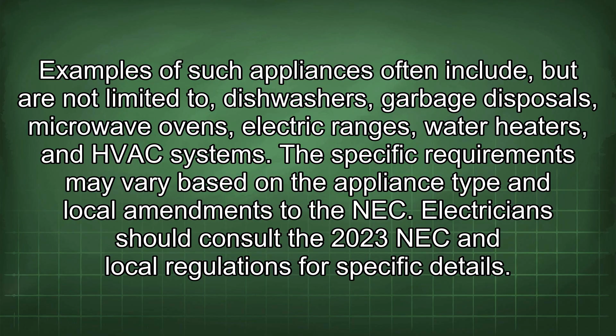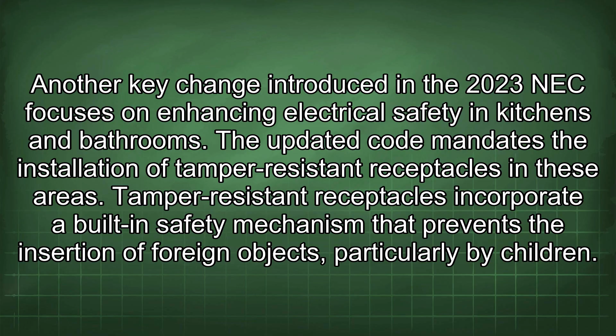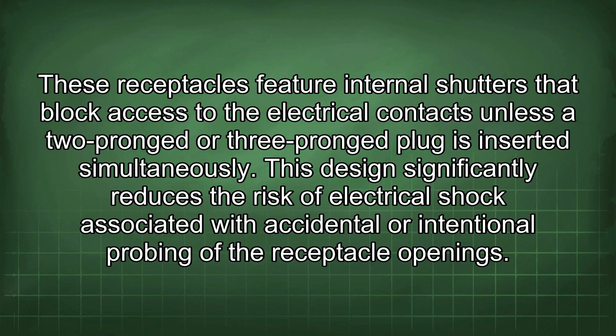Another key change introduced in the 2023 NEC focuses on enhancing electrical safety in kitchens and bathrooms. The updated code mandates the installation of tamper-resistant receptacles in these areas. Tamper-resistant receptacles incorporate a built-in safety mechanism that prevents the insertion of foreign objects, particularly by children. These receptacles feature internal shutters that block access to the electrical contacts unless a 2-pronged or 3-pronged plug is inserted simultaneously. This design significantly reduces the risk of electrical shock associated with accidental or intentional probing of the receptacle openings.